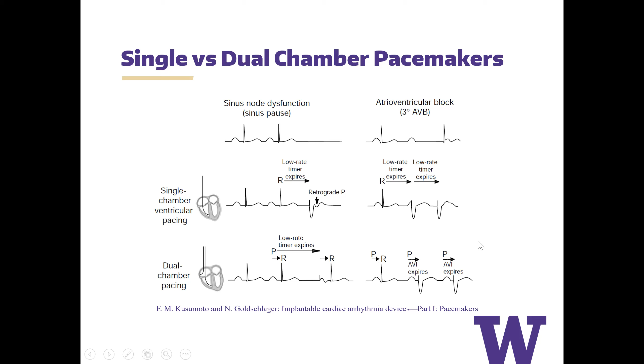Okay, so going through some of the common modes. In the mode of VVI or VVIR, again, this mode paces the ventricles at the end of the lower rate limit when there is no sensed V beat, and it paces and senses only in the ventricle. It will inhibit when there is a sensed ventricular beat outside the refractory period. And again, it's timed from each QRS, whether it's paced or intrinsic. The lower rate limit is the longest time that is allowed before delivery of the pacing impulse and is set by the programmed lower rate.